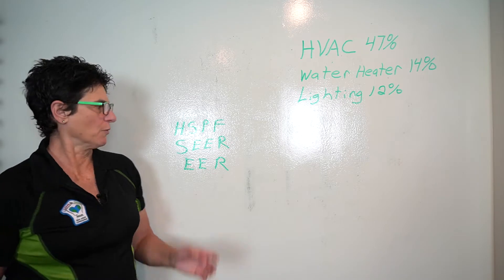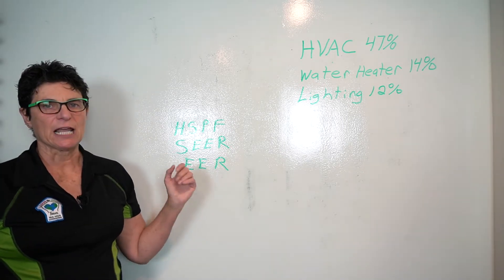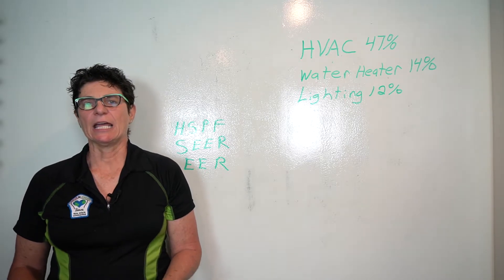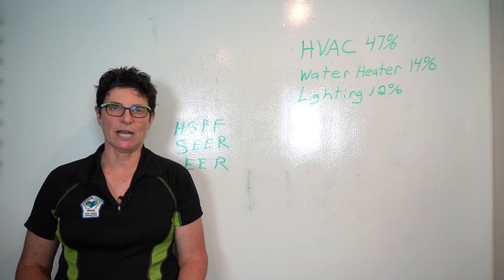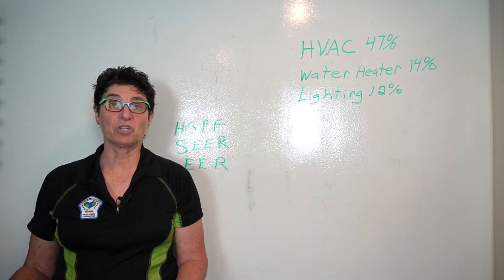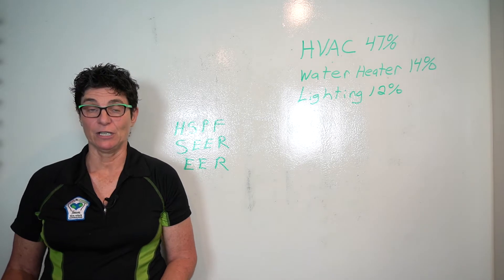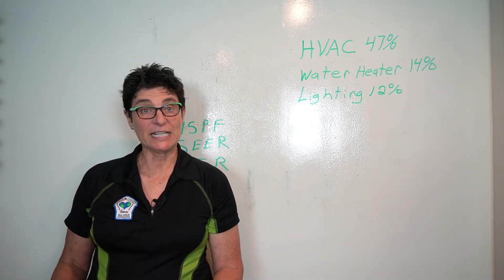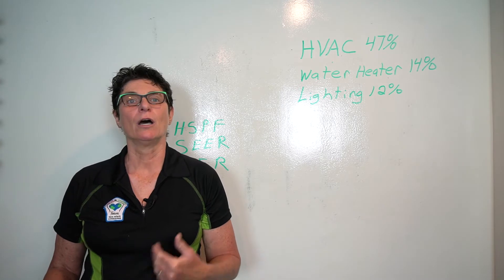What we're really focusing on in our area today, especially since it's getting hotter in western North Carolina, is the SEER rating and savings with the SEER rating. Basically, the higher the SEER number, the more efficient it is. At one point you can have more savings and get a good return on your investment. If you have an old house from the 1980s or older with air conditioning, it's probably a SEER 10 — that's really inefficient. Now we're working with SEER 14s on code. If you placed a SEER 14 in, you would save $194 a year off of your SEER 10.